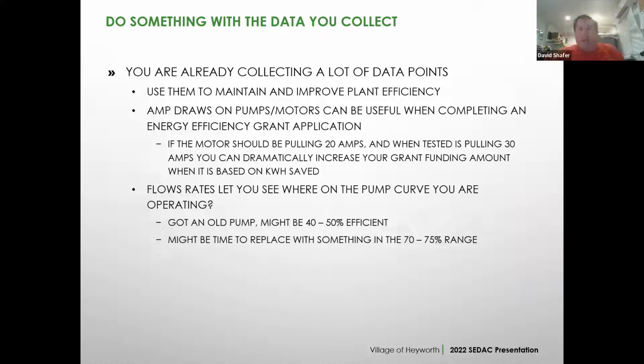So what do you do with the data that you collect? You want to use it to maintain your plant efficiency and improve where you can. You can also use it to your advantage when applying for energy efficiency grants. Like I said, if the motor is supposed to be pulling 20 amps but when tested you pull 30 amps, you can increase the amount of funding you're going to get, because a lot of the energy savings applications are based on kilowatt hours saved.